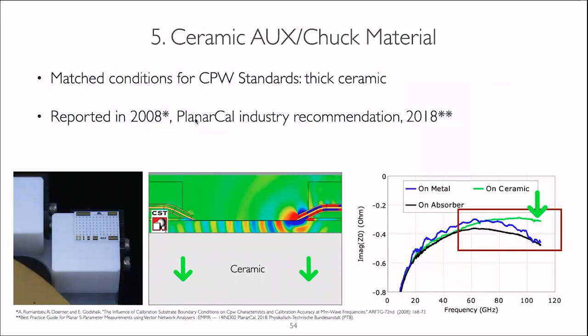The alternative approach is not to isolate the calibration substrate from the impact of the chuck, but to make the chuck itself from a matched material, a ceramic which has the same dielectric constant as the calibration substrate. The first experiments, done back in 2008, proved that this concept works very well. The main idea is not to absorb the electromagnetic waves, but just let them dissipate into the auxiliary chuck and make it infinite in size versus the geometry of the calibration substrate. This idea was already proven by the Planar-Cal Industrial Consortium of European metrologists and engineers. If we want accurate calibration using coplanar structures at frequencies beyond 50 GHz, it's better to look at the material properties of the main chuck and the calibration and auxiliary side of the chuck.